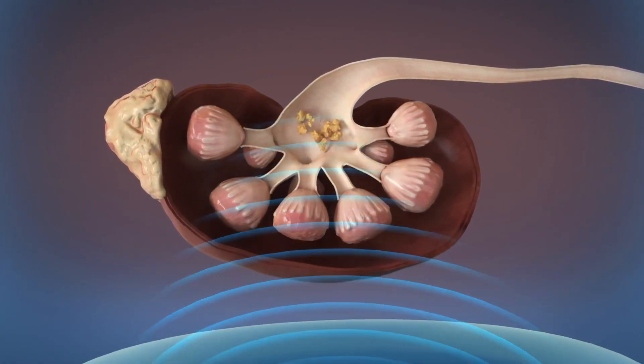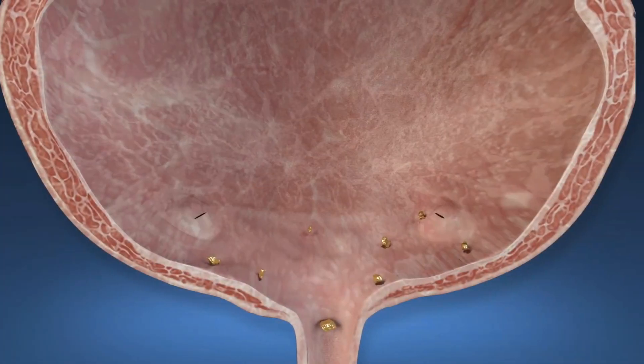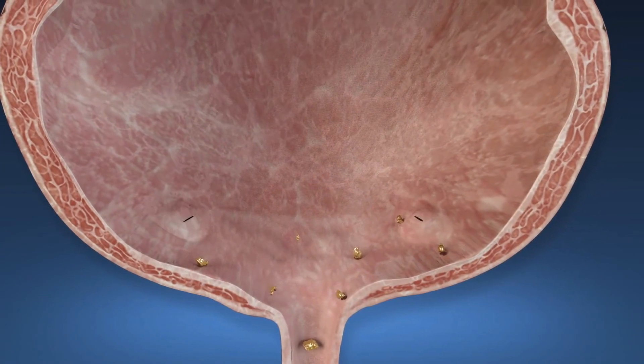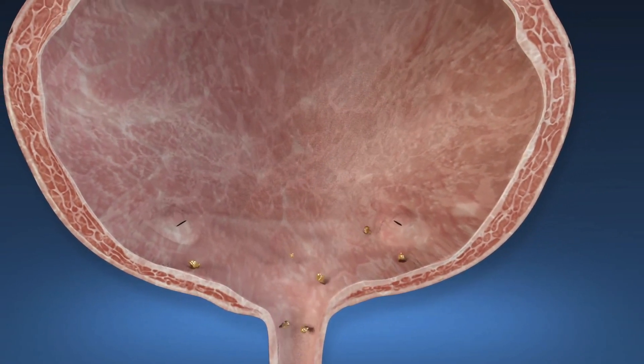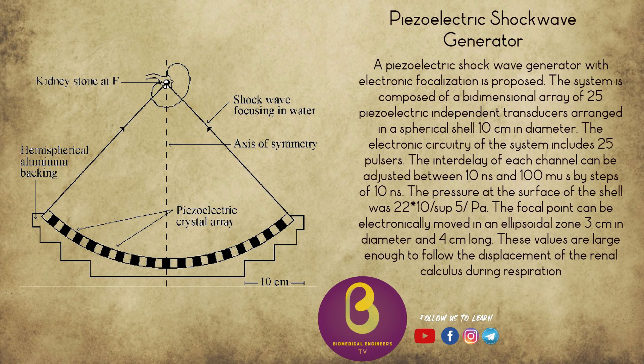The discharge of energy produces a vaporization bubble which expands and immediately collapses, thus generating a high energy pressure wave. The second type is piezoelectric. The piezoelectric effect produces electricity via application of mechanical stress.